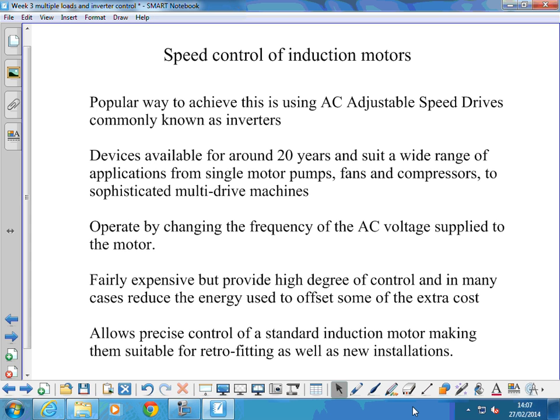They are fairly expensive, but provide a high degree of control, and in many cases reduce the energy used, which helps to offset some of the cost. And like all things, as technology moves on, they become cheaper and cheaper, with more manufacturers involved, they cut their prices, and become more and more cost effective. The biggest thing is that they allow precise control of what is generally a standard induction motor. The advantage is that they are good not only for new installations, they can be retrofitted. If we have a motor that doesn't need to run at full speed or full power all the time, we can fit an inverter retrospectively to that system.